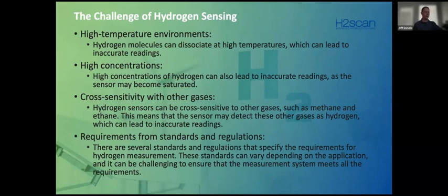One thing that we've noticed is that I've actually had sites that have called in and said, well, we're getting a carbon monoxide alarm, but they found out it was actually due to the hydrogen that was being given off from the battery. And so you can have cross sensitivities with other gases when it comes to sensors. So you just understand the type of sensor you have and the cross sensitivity that it could be occurring with your hydrogen sensor. And then, of course, we talked about the standards, codes and standards when it comes to regulatory.